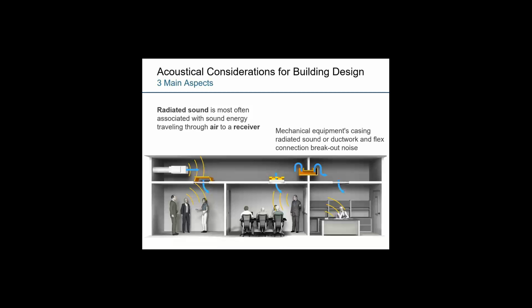Another type of consideration is radiated sound and radiated sound energy. Radiated noise is sound transmitting through a medium, typically the air, that is unducted and just moving directly from the source through whatever partition is present to the receiver. And this can often cause issues, whether it's in an open plenum above an occupied space or in an adjacent space transmitting freely through a wall or through a partition.